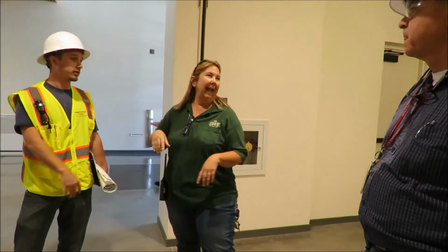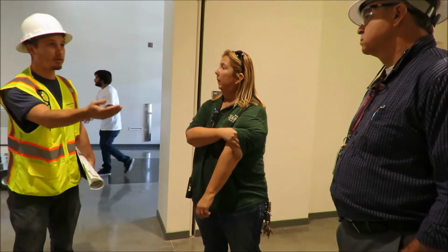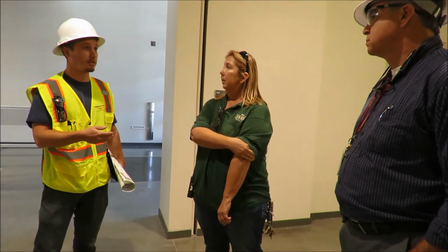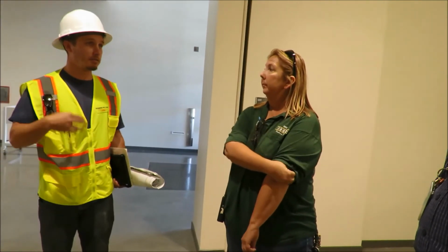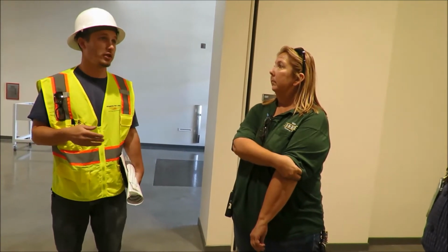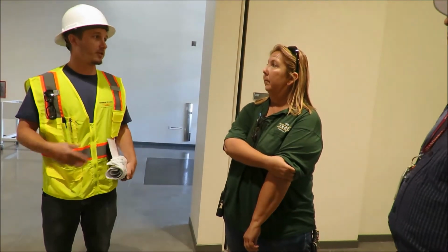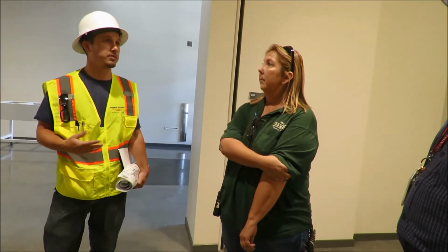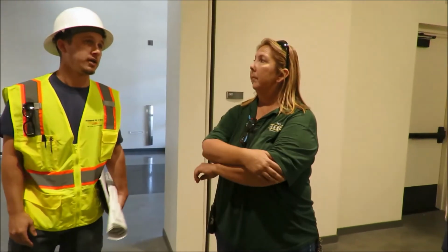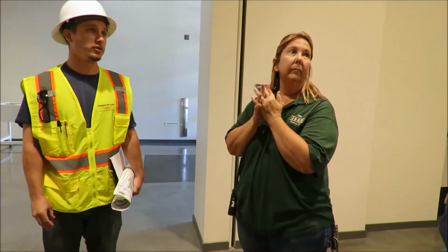The only thing I wanted to touch on briefly, which you may not know as much about, is the maintenance and testing of the system. We like to see an annual test done, a 100% test. If you get a lot of false alarms or something happening in a building, then you can bump it up to every six months. But typically, once a year, do a 100% test.